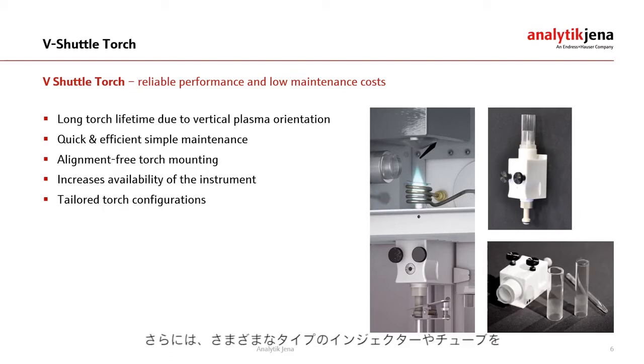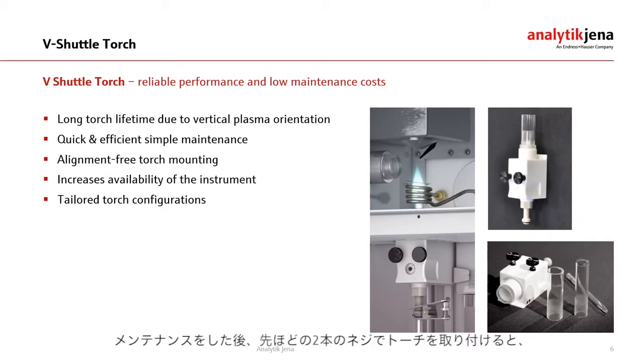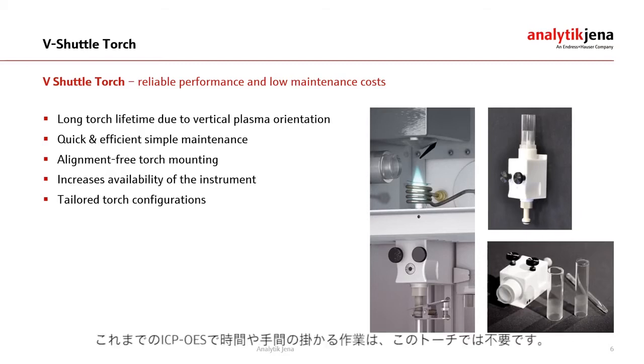Another advantage of a fully demountable torch is that you can use tailored torch configurations by employing different types of injector and tube materials. The torch itself can be easily removed by loosening just two screws. After maintenance, the torch is assembled again via these two screws and will then be aligned automatically by our unique shuttle mechanism. Time-consuming alignment procedures like those on other ICP-OES instruments are things of the past with this torch.